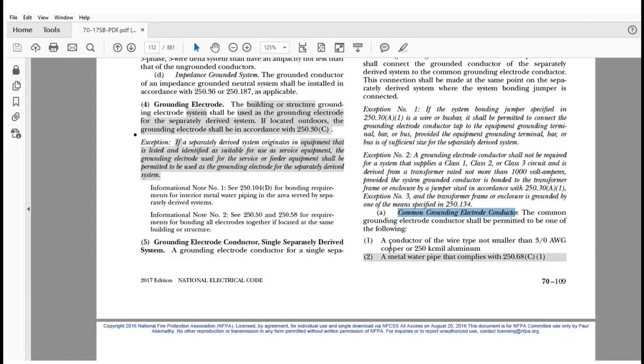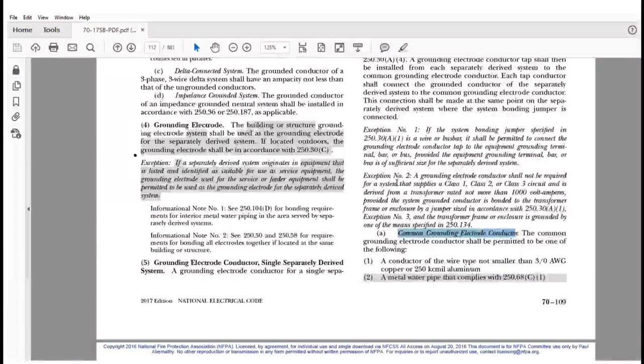The 2017 NEC, along with those revisions to the metal structural frame of a building, which, if you actually look back, and let me see if I can go back here, it's the common grounding electrode conductor shall be permitted to be one of the following. And you see that it recognizes the metal water pipe that qualifies here. We're not so much talking about the electrode, we're talking about a metal water pipe that actually can extend that connection as described in 250.68(C)(1). So you need to go look at that change if you're unfamiliar with this application.